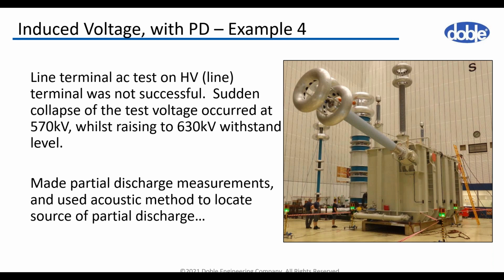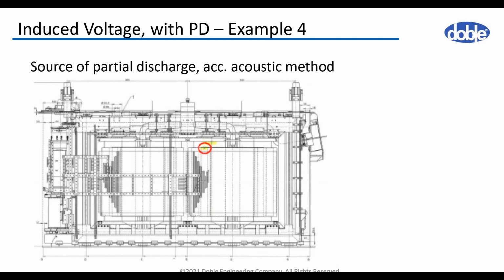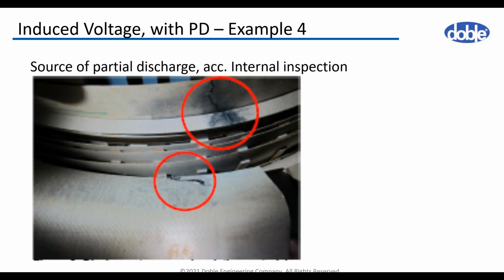The investigation of this problem continued with another PD measurement, an acoustic one, with sensors located at different places on the tank in order to find where the source of the PD is. This is where we found the PD activity within the active part. We were able to locate it, which made the further failure investigation much easier. Following the localization of the PD activity, the transformer active part was taken out of the tank, and we performed an inspection. We found the faulty area.